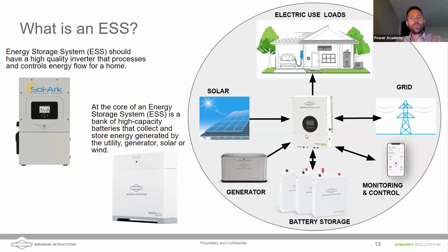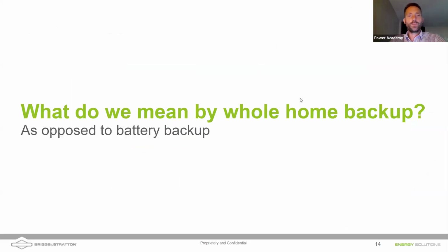At the heart of an ESS system is an inverter, and that manages multiple sources of power. And you can use multiple sources of power simultaneously. So for instance, if your home loads are consuming, let's say, 10 kilowatts and you only have 7 kilowatts of solar coming in, the batteries are capable of supplementing that 7 kilowatts of solar and covering the full load so that you're not having to buy from the utility, which would typically be more expensive.